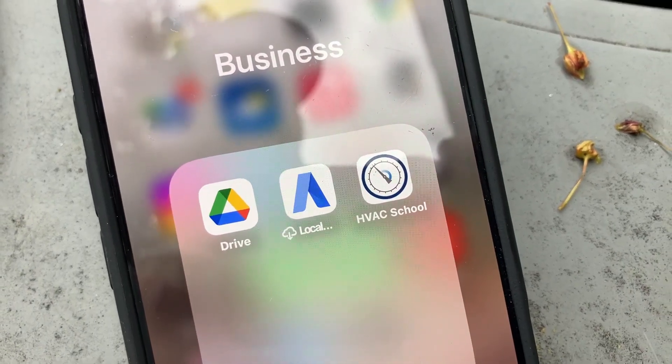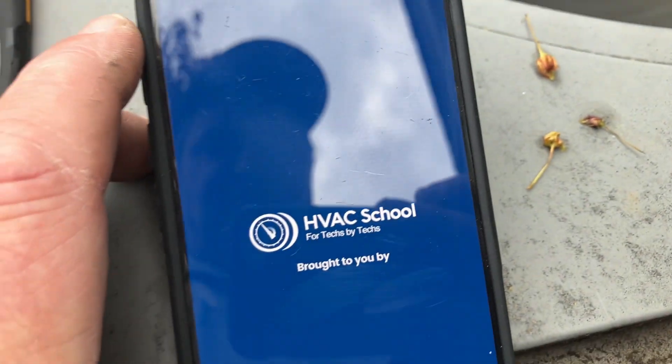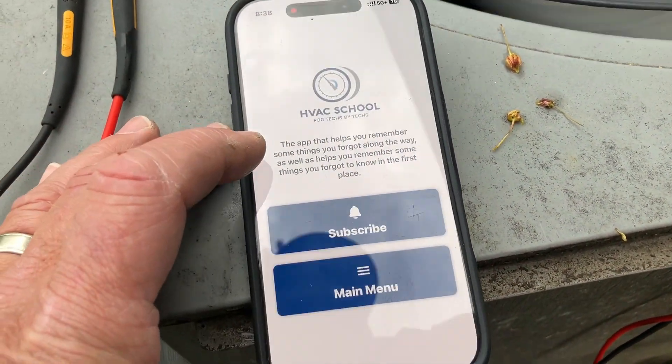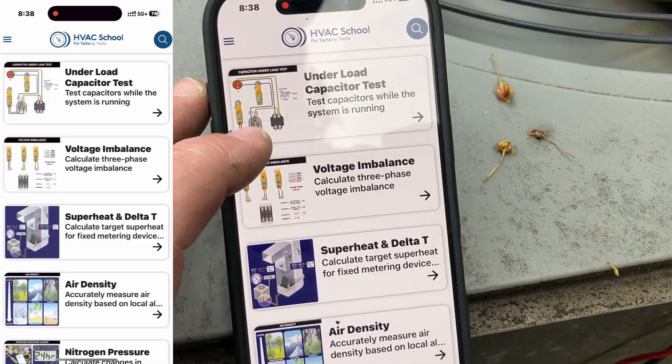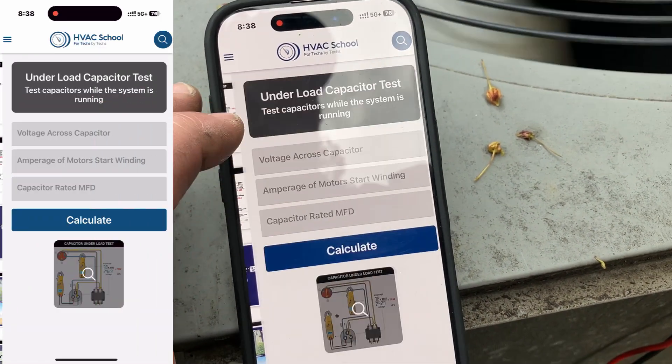All right, to test the dual capacitor dynamically I'm using the HVAC School app. Inside the app, once you get past the Refrigeration Technologies ad, we're going to go to Main Menu, then Tools, and I'm going to go to Under Load Capacitor Test.